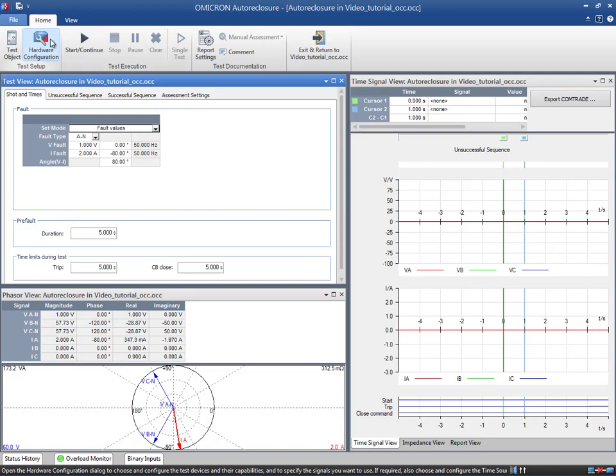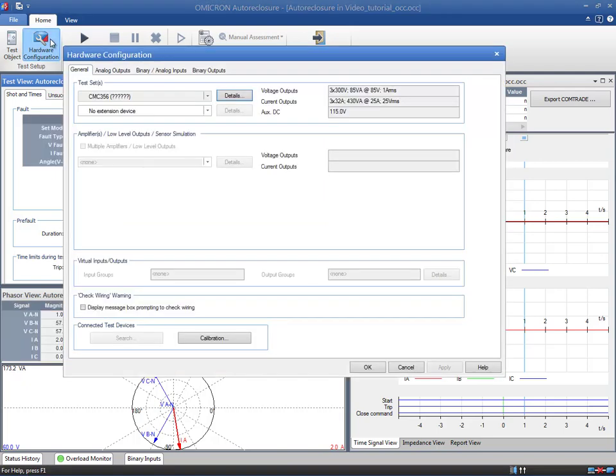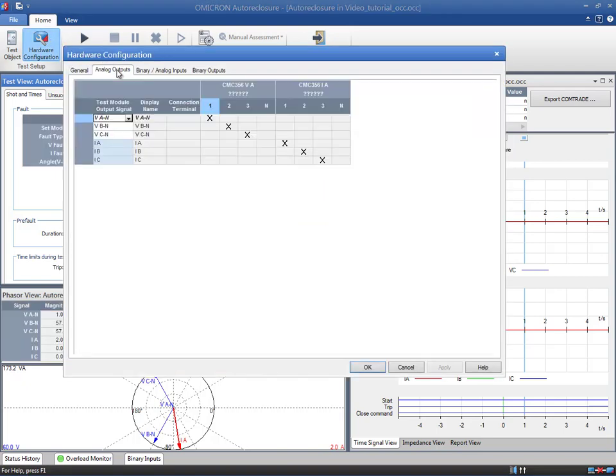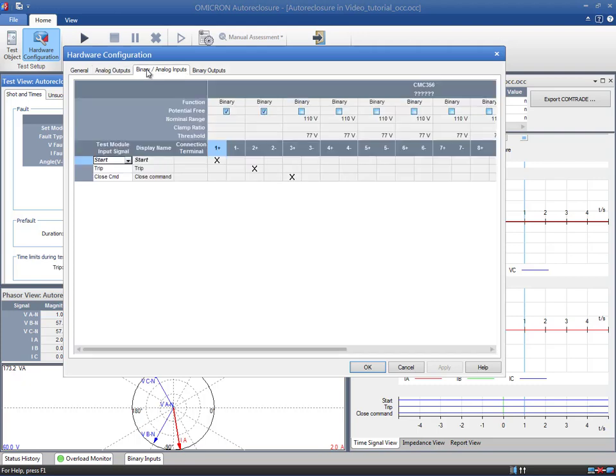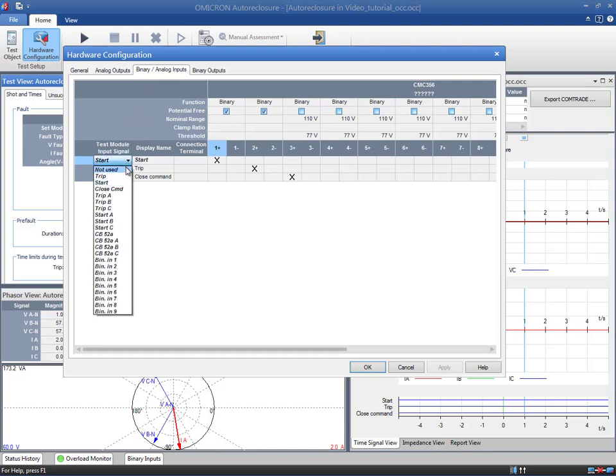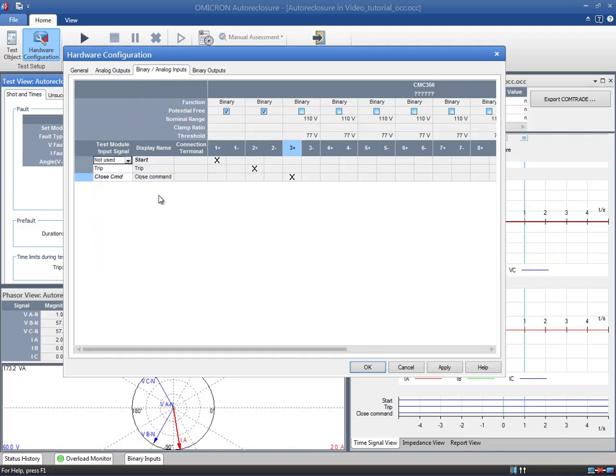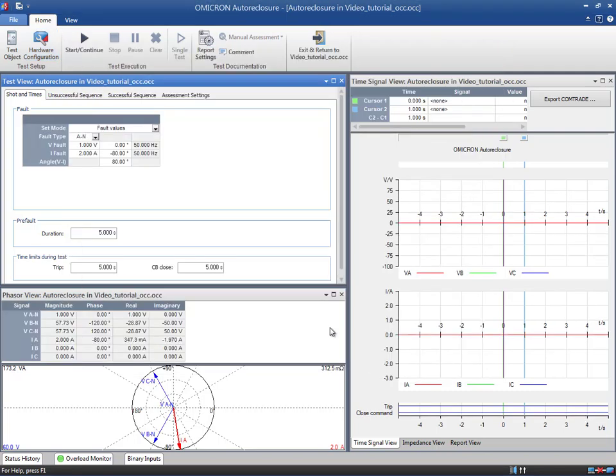Now we start with the local hardware configuration. The voltages and currents are required for this test. Additionally, we need the Protection Relay's Trip command and the Circuit Breaker Close command. In the first tab, you can define the fault settings. In our example, we will simulate a fault within the extended zone so we can check whether this zone is active or not.